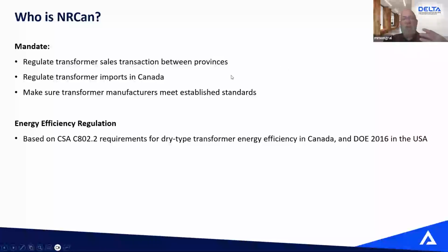So when there's a change from NRCan, all the provinces will follow pretty much at the same time. So it makes business much easier for transformer manufacturers. So mainly, again, NRCan is the law. That's the government. They make a law. And then what do they use for standards for efficiency and everything? So in Canada, we use the standard from CSA called CSA C802.2, which is the standard for minimal efficiency and test procedure for dry type transformers.